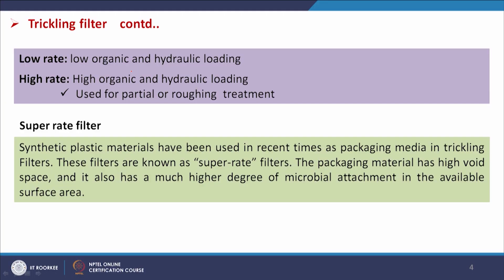In the case of trickling filters, there may be low rate, high rate, and super rate types. Low rate means low organic and hydraulic loading; high rate means high organic and hydraulic loading, used for partial or roughing treatment. The super rate filter uses synthetic plastic materials as packing material. This packing material has high void space and a much higher degree of microbial attachment in the available surface area.